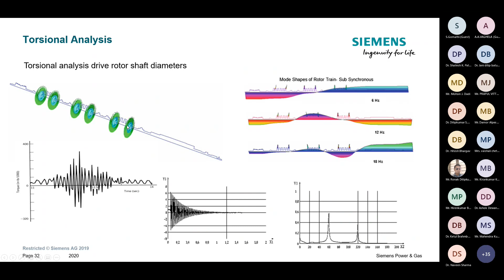Even blades also. By the way, this is the rotor train of a nuclear power plant in the USA, where I performed this torsional calculation. And you see these are the blades. The last stage blade also has a very big inertia, and it also tries to vibrate, in positive and negative directions. If that happens continuously, imagine that with every rotation, positive and negative, it will fail instantaneously. We call it high cycle fatigue. So we don't want that.